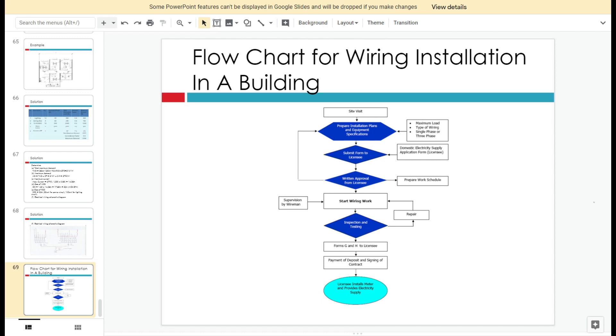After the site visit, you review the project plan. The architect will provide the architectural layout plan, from which you identify what equipment is needed. Then you perform the load calculation: identify the demand factor, calculate the total connected load, and identify the maximum current, in order to determine what type of system to use.